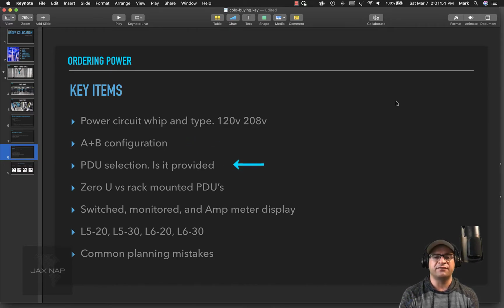You have to find out if the data center is actually going to provide you with the PDU or you're going to have to provide it yourself. You're also going to have to find out if it's a 0U PDU or if it's going to be a rack mounted PDU. Switching and monitoring is important on the PDU. You want to make sure you can actually do your own reboots if possible, and you want to see what your usage is as well. So you also want to make sure there's an amp meter display on the PDU.